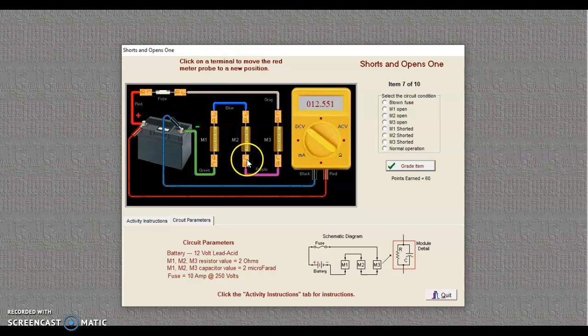And I'm starting with a source voltage of 12.5. And, again, I'll take this middle strategy here. We'll go right to the center. And we see that we have 0 volts between my probes. That means something back here on this side, M3 or my fuse, is open. So let's go on the other side of M3. Ah, I got all my source voltage.